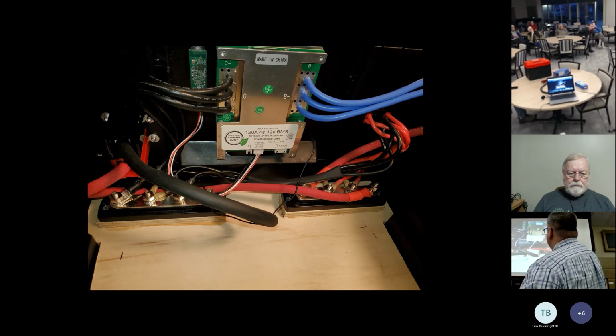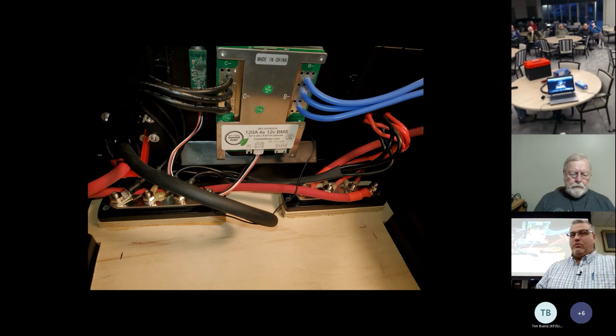Underneath this actually functions as some heat sinking into that space should it need it. But the MOSFETs have a very low voltage drop, so they're able to switch that load very efficiently without a lot of voltage drop or heat buildup. The entirety of its purpose is it also protects from over discharge, so if it exceeds 120 amps, it will cut it off at the BMS. I've got short circuit protection in the top of the box, but it will cut it off at the BMS level as well.